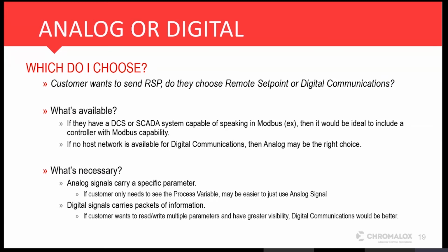So if they're only asking for one thing, they probably don't want to go through the whole process of mapping the controller just for that one parameter when they can just send a simple analog signal and be done with it. But if they are going for more of the information, more of those parameters, you can't really do that reasonably in an analog configuration. You're best to go through the digital. So if you ask yourself those two questions, you can really key in on what they're going to need or what they're going to want to use.